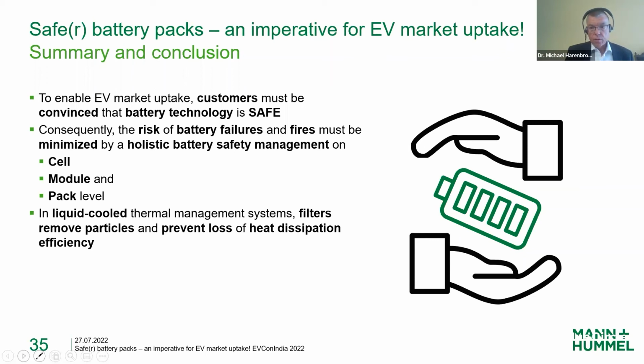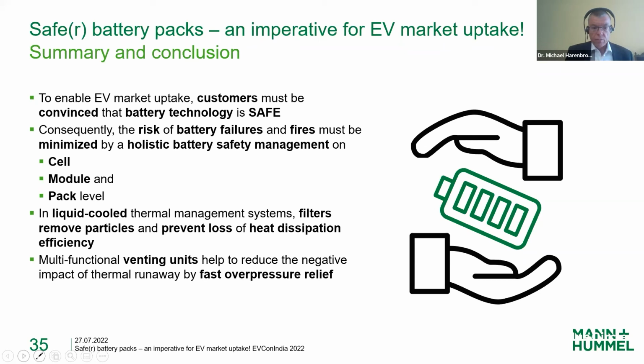So two solutions which can contribute to that I've shown you in this presentation. On one hand, for liquid-cooled thermal management systems, to integrate filters which make sure you don't have any blocking of cooling channels, and that you don't have pump wear, which would reduce the heat removal efficiency of your cooling system. Those multifunctional venting units can also help through fast relief of overpressure, so you prevent the massive buildup and explosion afterwards of battery packs. It can also help reduce the risk of battery fires by integrating hot particle filters.